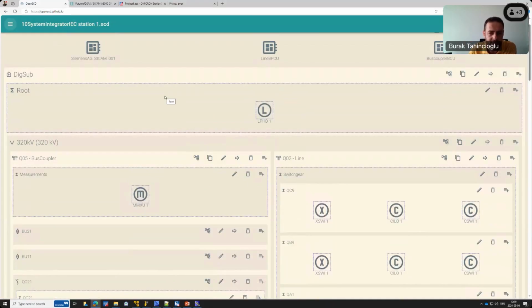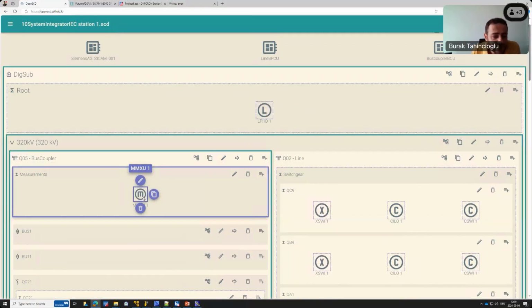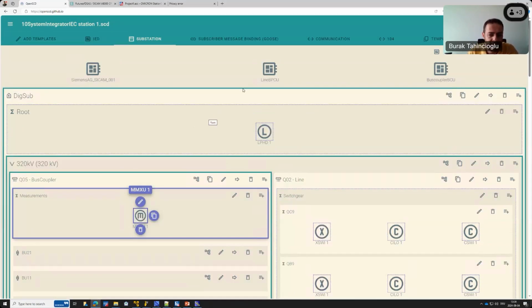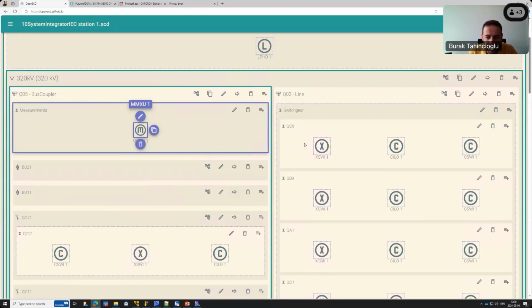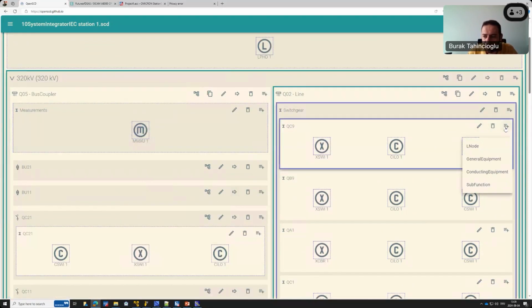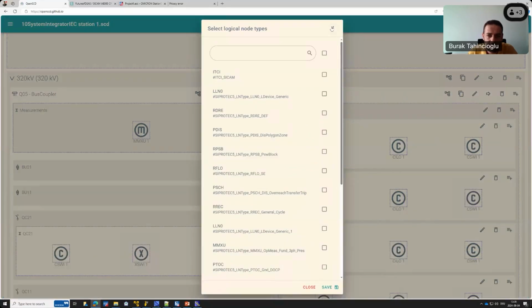You might be confused because we assigned the functions to data type templates, not to instantiated logical nodes—there's a difference. The data type templates section is where we freely create our IED, but here we need to do something else: assign the logical nodes, for instance of the physical switchgear, to the instantiated logical nodes. We do it from here, at reference to existing logical node, not the templates.